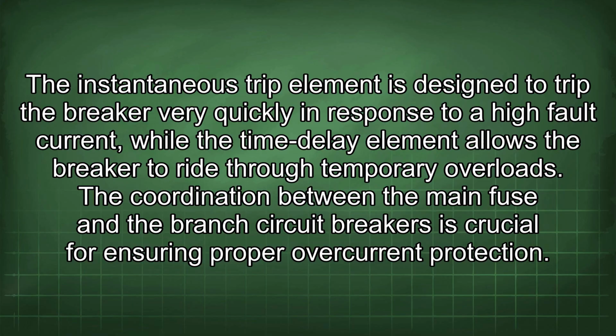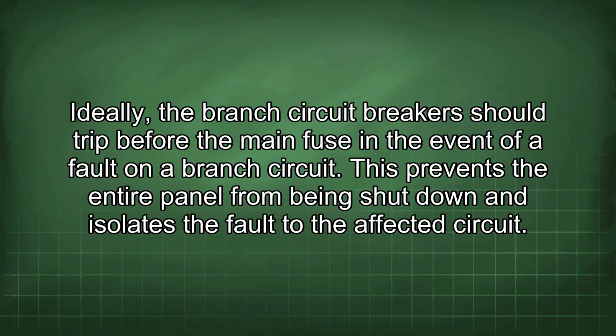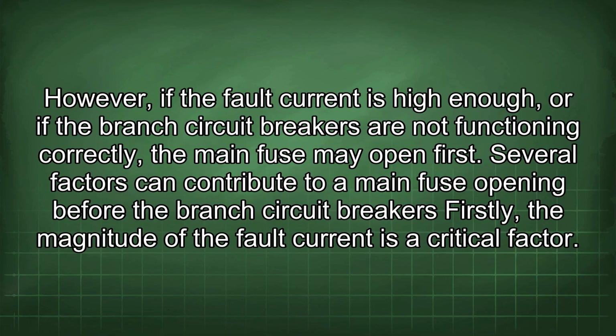The coordination between the main fuse and the branch circuit breakers is crucial for ensuring proper overcurrent protection. Ideally, the branch circuit breakers should trip before the main fuse in the event of a fault on a branch circuit. This prevents the entire panel from being shut down and isolates the fault at the affected circuit. However, if the fault current is high enough, or if the branch circuit breakers are not functioning correctly, the main fuse may open first. Several factors can contribute to a main fuse opening before the branch circuit breakers.